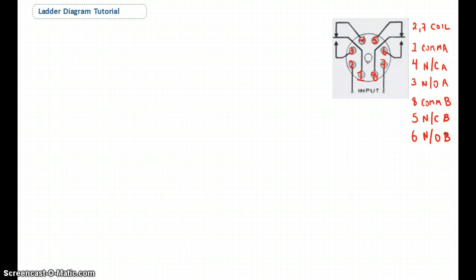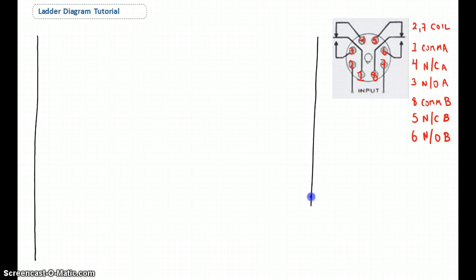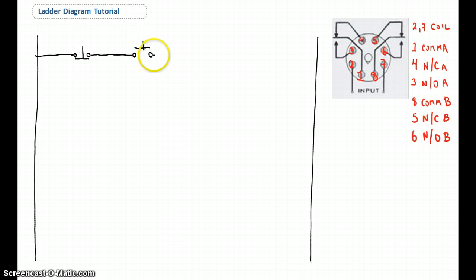Now we've got an 8-pin relay and we're going to use it to create components within our ladder diagram. There aren't really any decent programs out there to simulate this, so I'm going to draw out the diagrams. We'll start with two lines — our feed and our return for the ladder diagram. Say we needed a stop/start station: we come off the line, drop in a normally closed push button, come over to a normally open push button, and feed the relay.